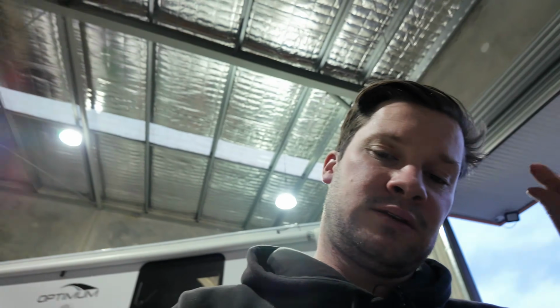Now because it's a 5 kVA MultiPlus, we've got to do things a little differently. Instead of running one 70mm cable like we do for the 3 kVA MultiPlus, with the 5 kVA you've got to run two 70mm squared cables, 2 cores for the active and 2 cores for the neutral, whereas with the 3 kVA you can get away with running one.